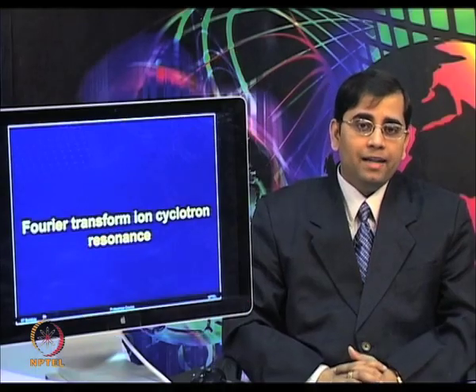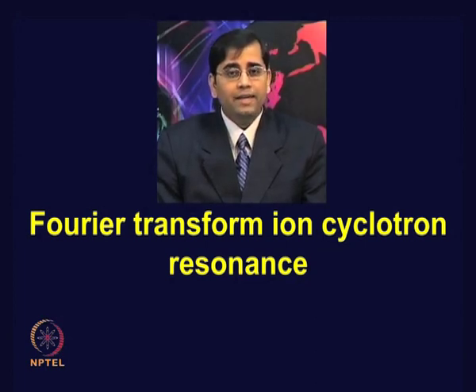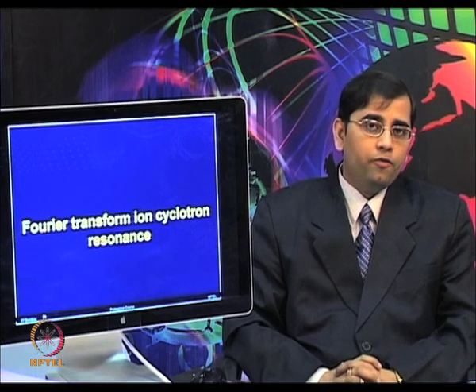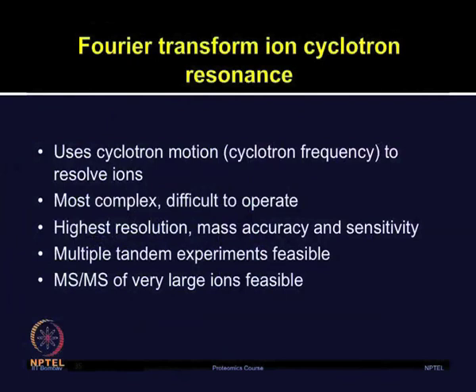One important mass analyzer is Fourier transform ion cyclotron resonance, or FTICR. Due to its high resolution and MS/MS capabilities, FTICR MS in combination with electrospray ionization has been employed for large biomolecules and is also used in proteomics. An FTICR MS can be considered as an ion trap system where ions are trapped in a magnetic field. It uses cyclotron motion or cyclotron frequency to resolve the ions. Although operationally it is very complex and not easy to operate, it provides the highest resolution, mass accuracy, and sensitivity. It also provides capability for multiple tandem experiments, and MS/MS of very large ions is possible.